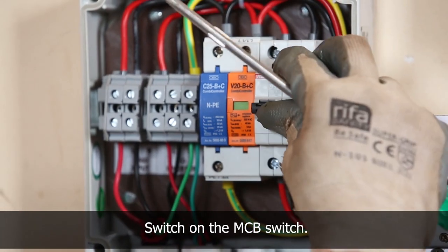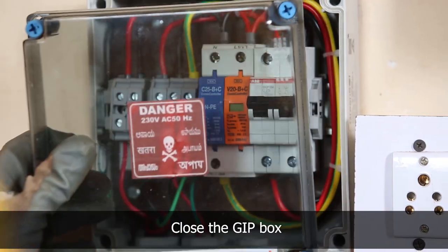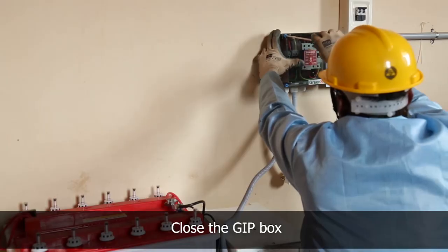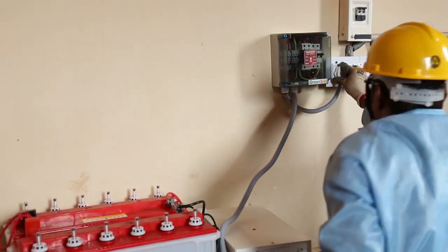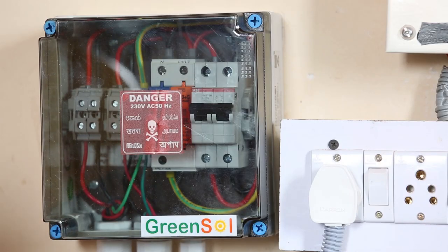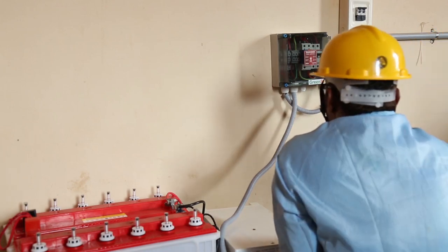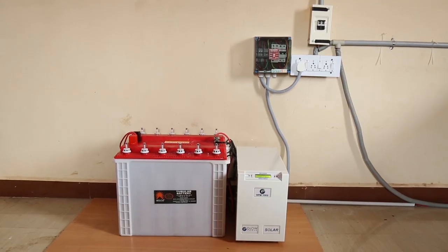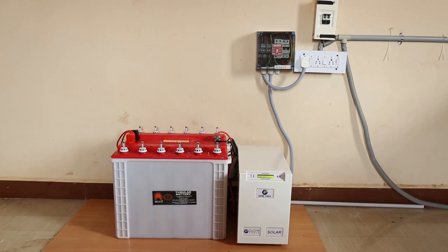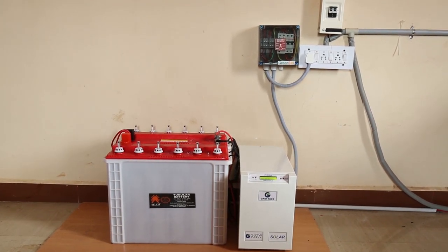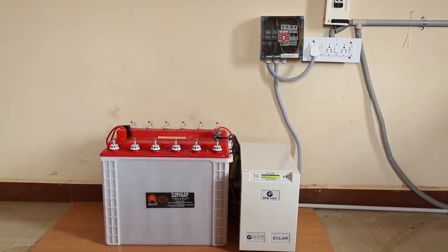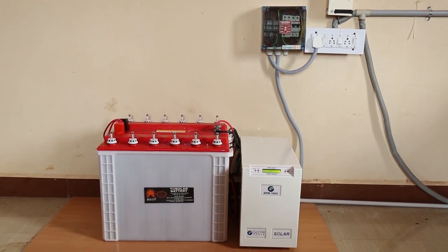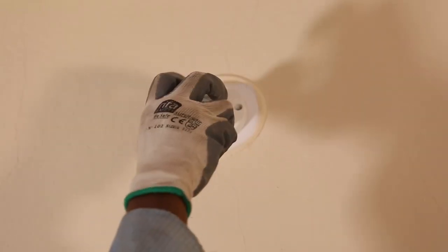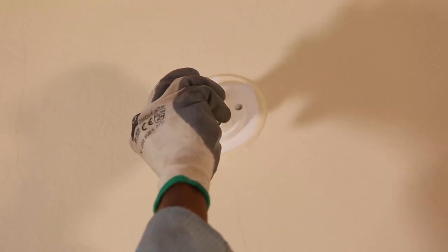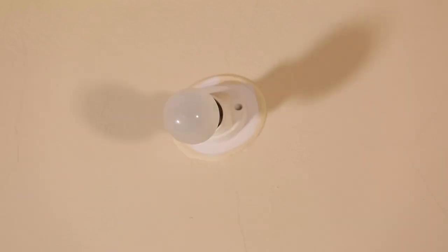Now, turn on the miniature circuit breaker switch and cover the grid input protection box. Connect the plug from the grid input terminal of the grid input protection box to the grid. The power conditioning unit connection is complete and the load is to be connected to the output terminal of power conditioning unit. Switch the old luminary with the new one and test to see if it is working.